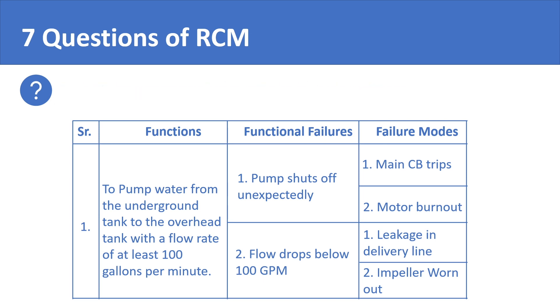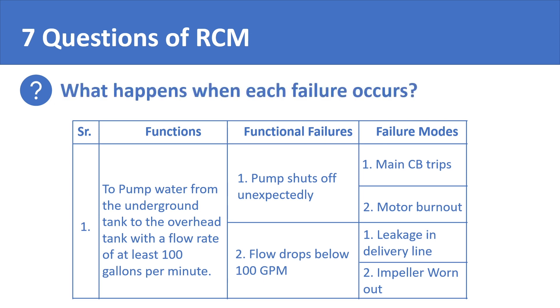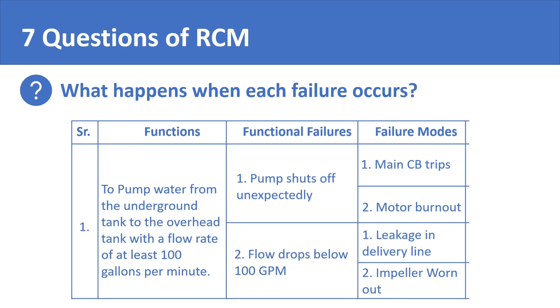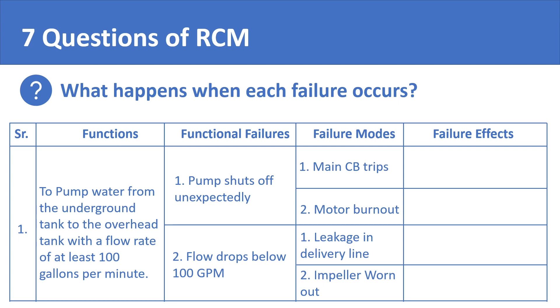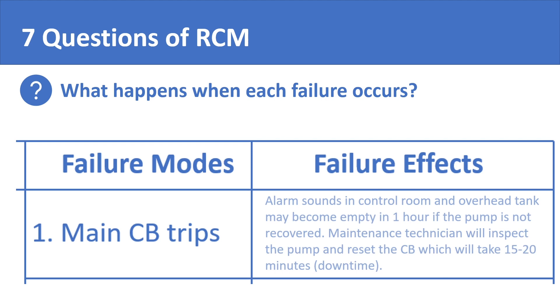The fourth question of RCM is: what happens when each failure occurs? That is to say, what are the effects of each failure? For example, the effect of a circuit breaker tripping would be that an alarm sounds in the control room, or maybe a red light flashes over the pump to grab the attention of operations people. In this way, the fourth step of RCM is to figure out all the different types of failure effects.